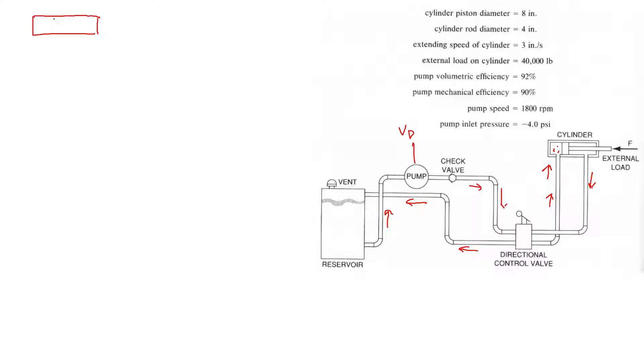The first question asks us to find the volumetric displacement (VD) of the pump. To find VD, we first need the theoretical flow, and to find that we can start with the actual flow. We have the velocity of extension and the area of the piston. Thinking of the piston extending at 3 inches per second through the fluid, velocity times area gives us the flow rate. So Q_actual equals area times velocity.